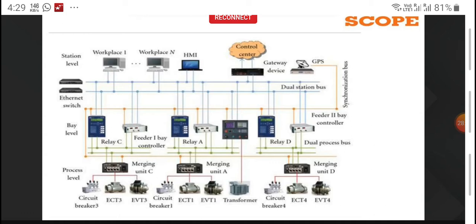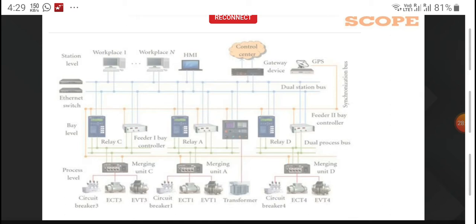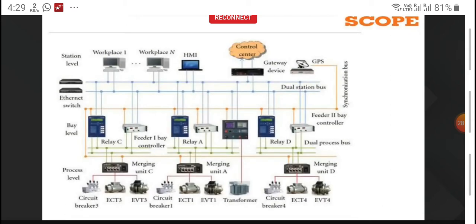From here to the relay, the complete signals are on optical fiber. Normally the 61850-9-2 protocol is used to send these CT and PT signals to the relay. The relay we are using today may not support these digital CT and PT signals, so your relay must support the 9-2 protocol.